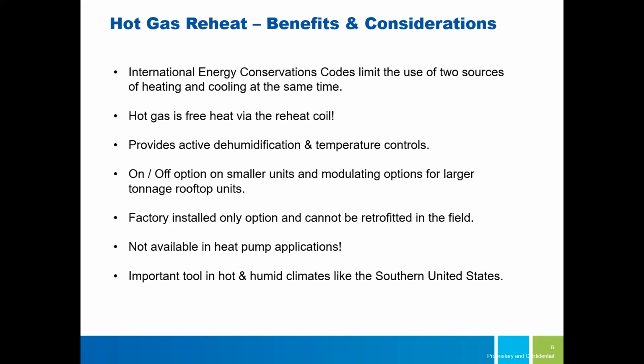Now, what I have seen is there are some people that will trick the heat pump basically into running the cooling and the heating simultaneously, unofficially. And by the way, technically you're not supposed to do that because it doesn't meet code in some cases. But I will say, in a residential application, I have seen where there is apparently an option where a manufacturer allowed you to disable that lock on the board, because in North Carolina, the energy code specifically says you can't. The thermostat has to lock it out so that when you're in one mode, you can't go to the other and run both simultaneously. So this kind of tricks out that stuff.